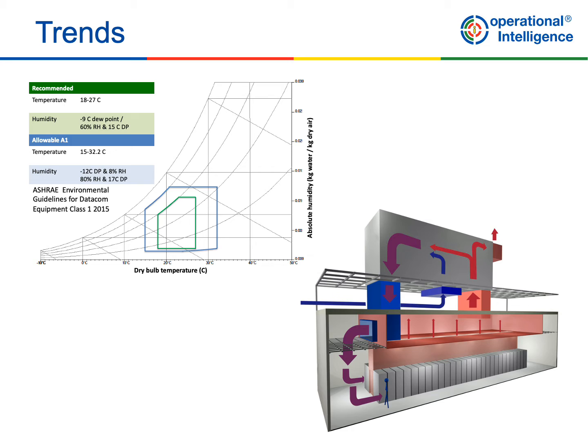We're seeing more data centres making use of free cooling. So the diagram on the right hand side is a particular design using direct fresh air free cooling. You'll see there's no raised floor and the air is delivered via a roof mounted air handling unit, which is supplying air to the facility below.